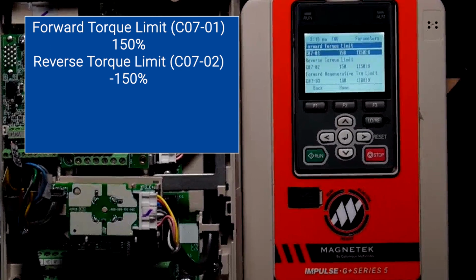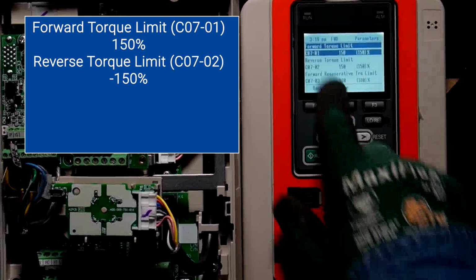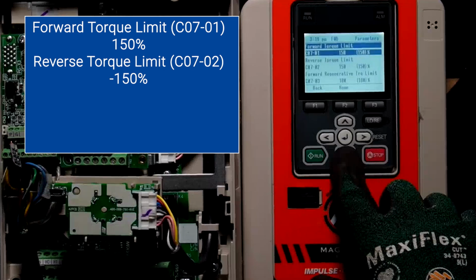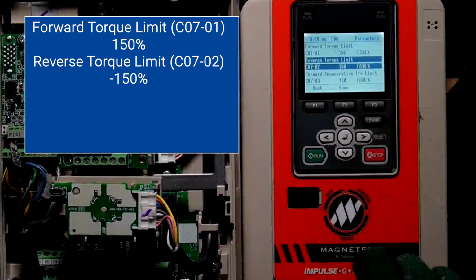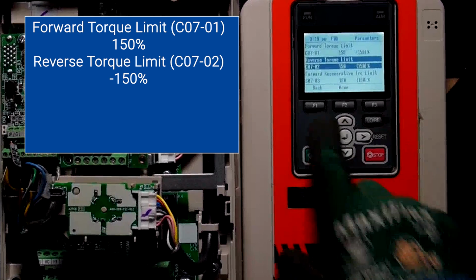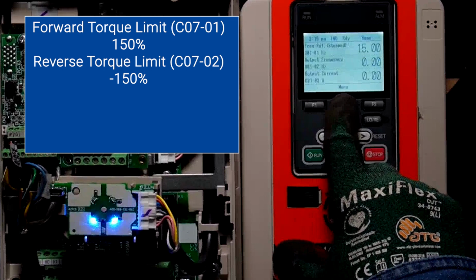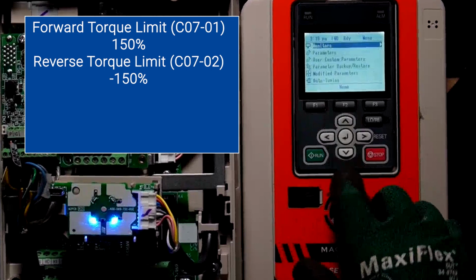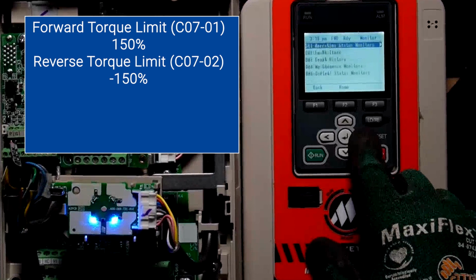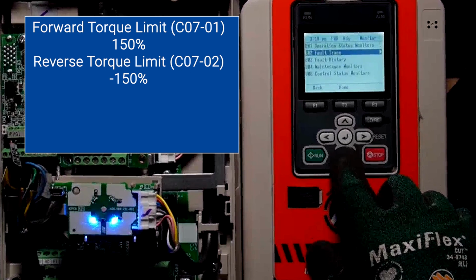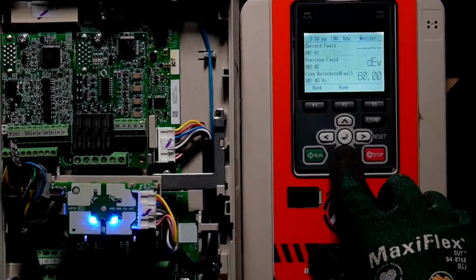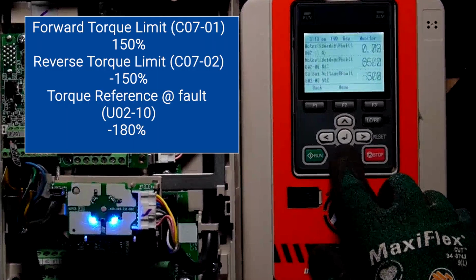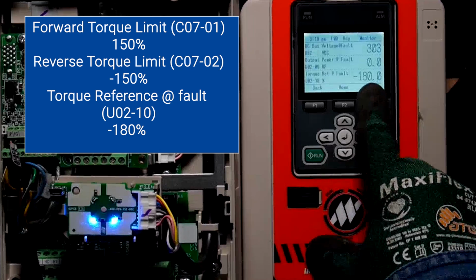Now, we saw that when the drive tripped on a DEV fault, it was at a minus, which is going to be important, 180%. The minus indicates actually the reverse, or if it was a hoist, the down direction, that's set to 150%. Okay, we're going to go back. Actually, we'll just go home, and we're going to go to the menu. We're going to look at the monitors again, and we're going to look at the trace data, and we're going to cruise down to that torque value. And again, you'll see it's minus 180%.